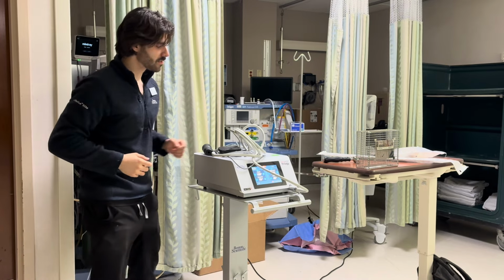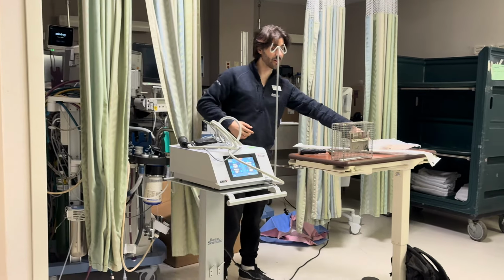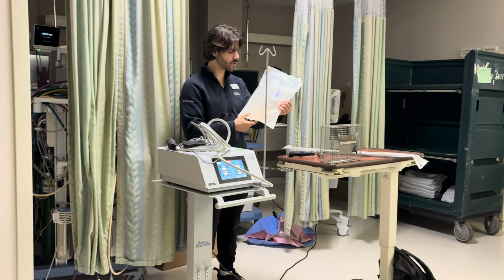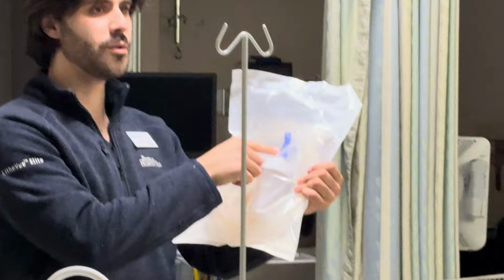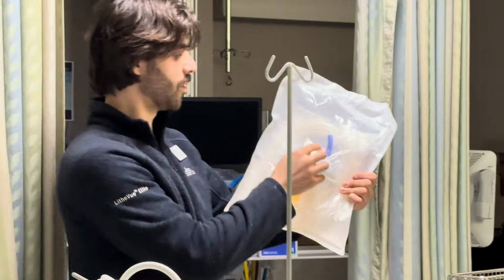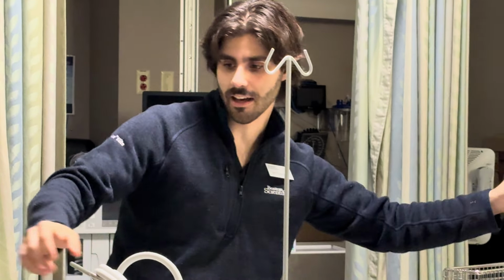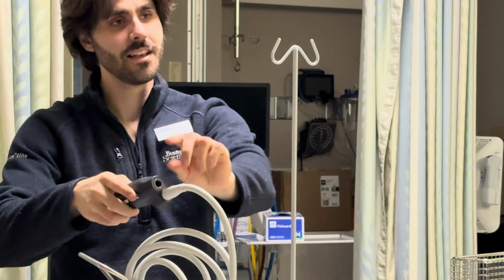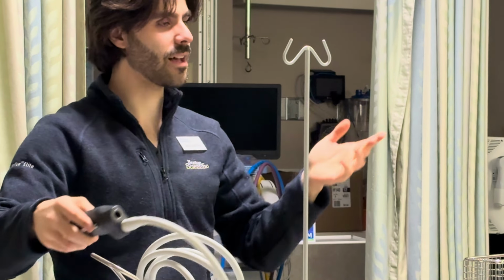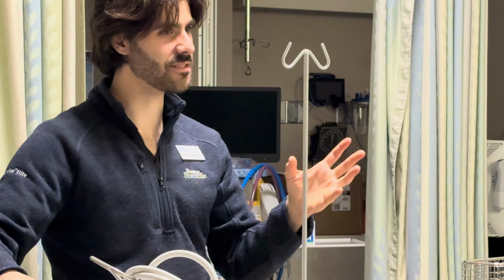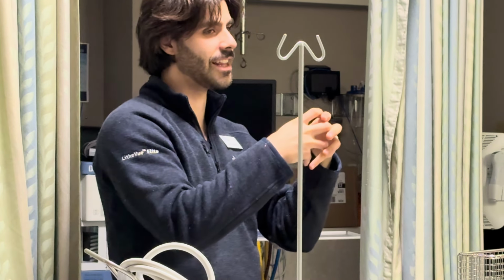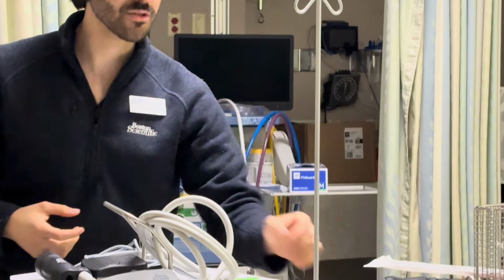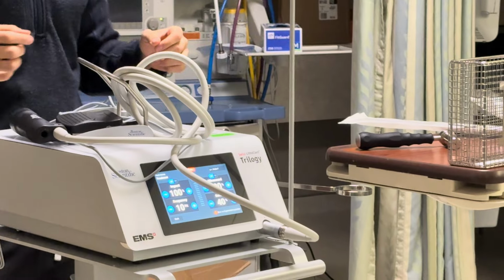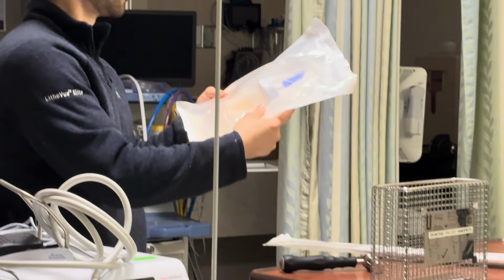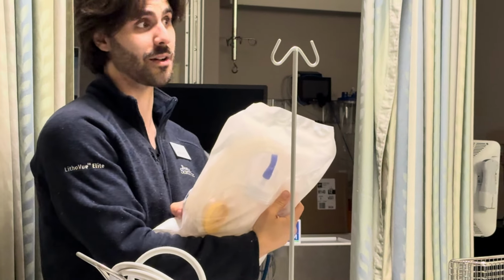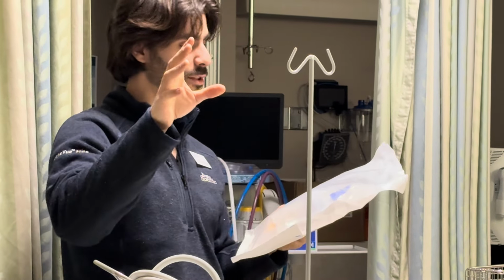Yeah, that's good. That's also a really common call that I usually get. So the tubing, there's a few different hotspots for blockages. One of them would be at the back of the handpiece. Anything that's going to have a bend at some point, especially if you have a really gummy stone, it can accumulate in there, and then maybe you're looking at your suction tubing and nothing's flowing. So it's really important to always keep an eye on your suction tubing as well, because the doctor's not going to be looking at it. They're going to be looking at their field.